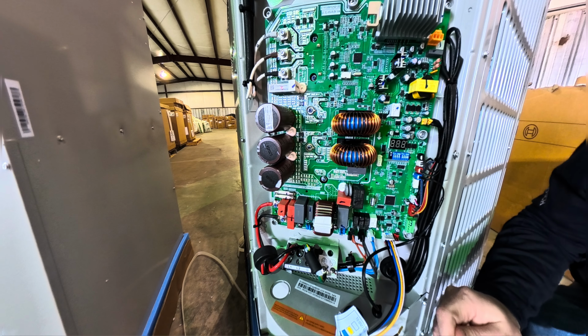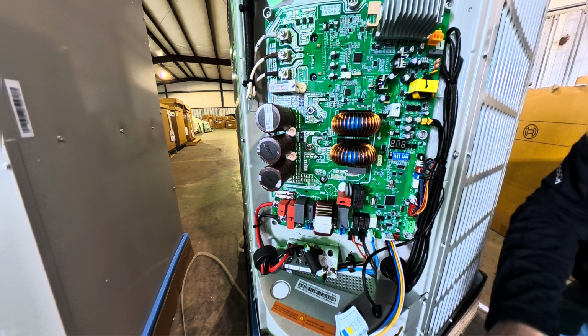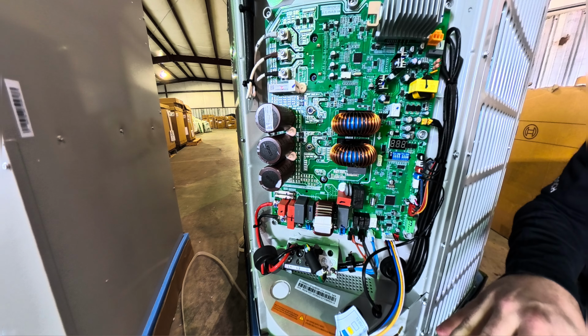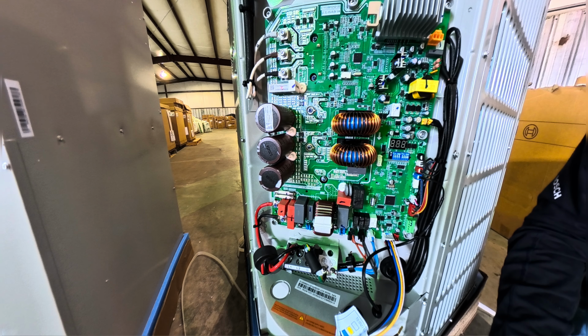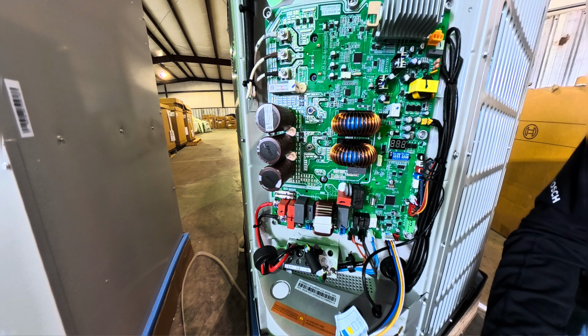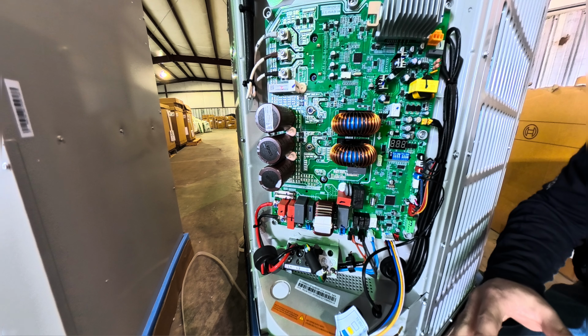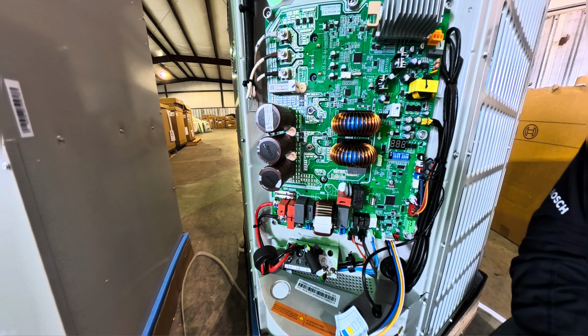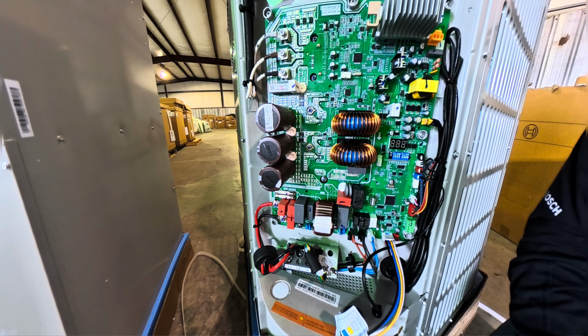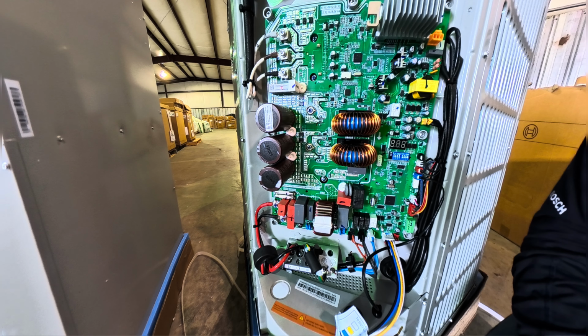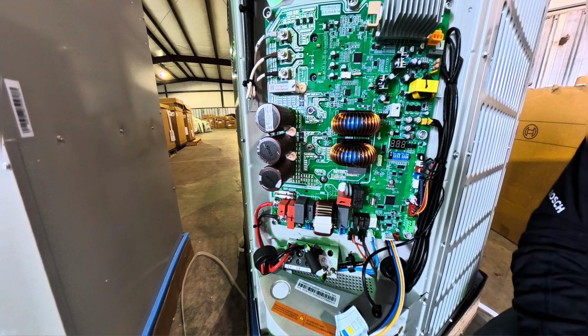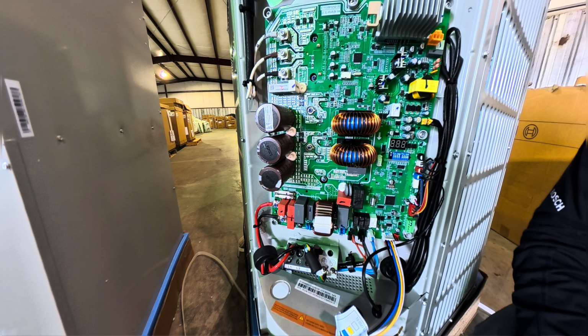It's going to tell you the opening of the EEV. It's going to tell you what speed the compressor's at, what speed the fan's at. It's going to tell you your suction and discharge pressures. So it's also going to tell you your amp draw of the fan motor and the compressor. You can leave your tools pretty much in the truck because you can see everything from the control board. You don't need to go into a thermostat to a $1,000 controller and look at data that way. You don't need an overcomplicated thermostat. You can use any thermostat you want.